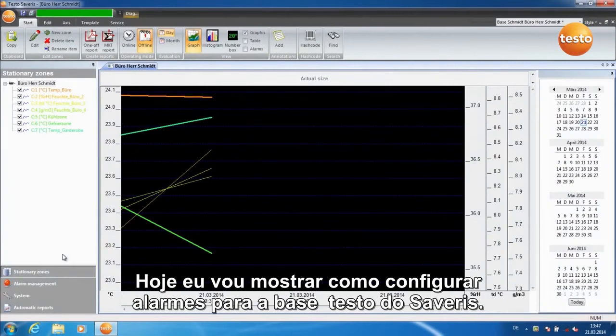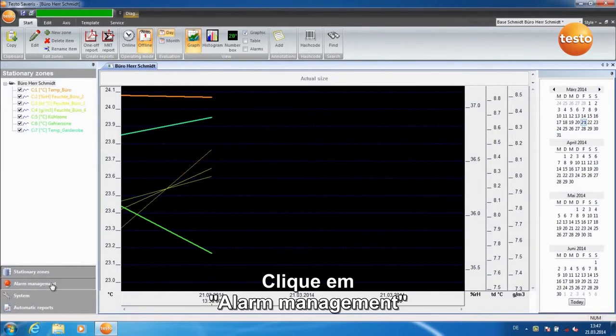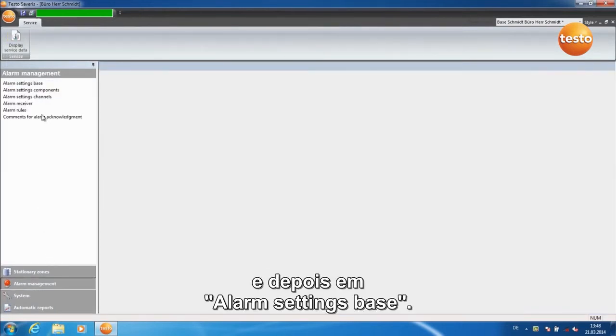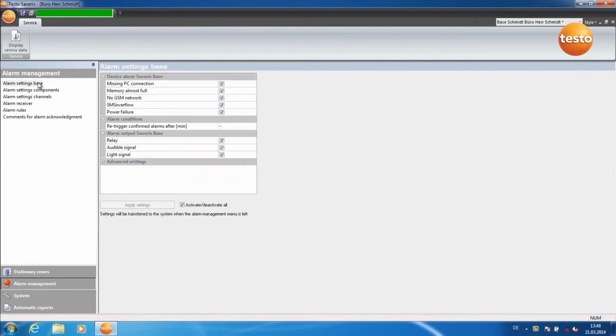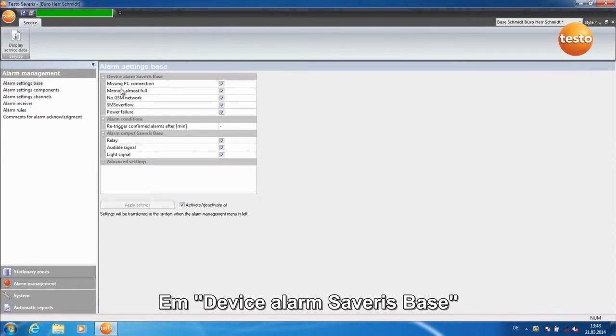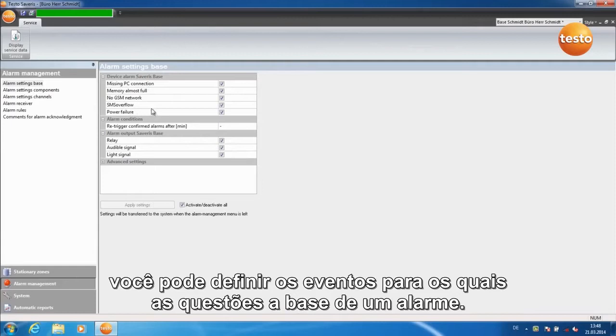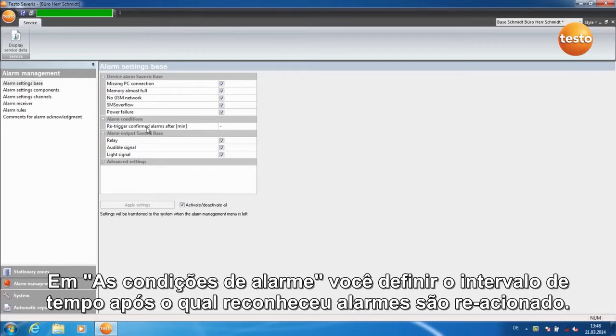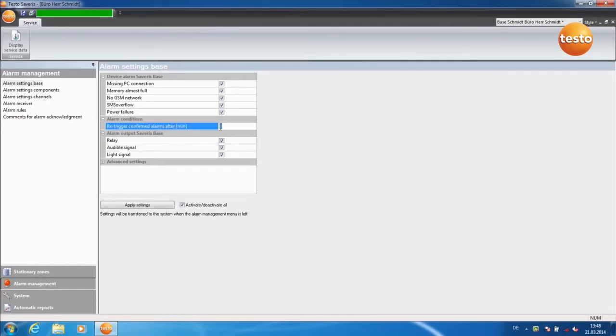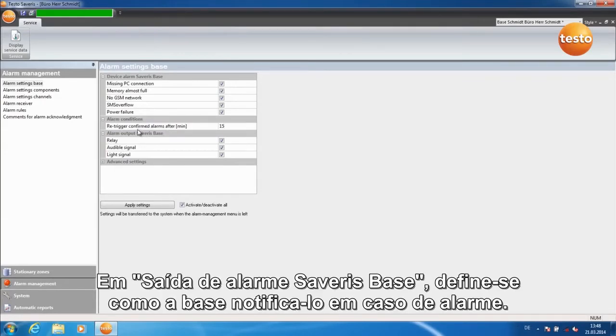Today I'm going to show you how to set alarms for the Testo Saveris base. Click on Alarm Management and then on Alarm Settings Base. Under Device Alarm Saveris Base, you can define the events for which the base issues an alarm. Under Alarm Conditions, you set the time delay after which acknowledged alarms are re-triggered. Under Alarm Output Saveris Base, you define how the base notifies you in case of alarm.